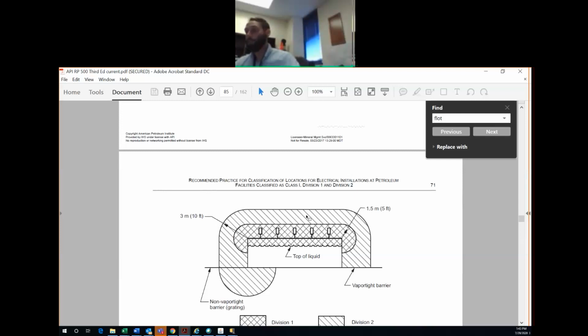I'd encourage all engineers who are reviewing these area classification drawings to take that into account and even maybe suggest to operators that they reevaluate their tanks, especially if they have leaking gaskets, to ensure that they meet the proper area classification. Class 1 Div 1 would be, in my mind, a more appropriate classification for flotation cells, given the incidence of gas release that we've had through the gaskets offshore.